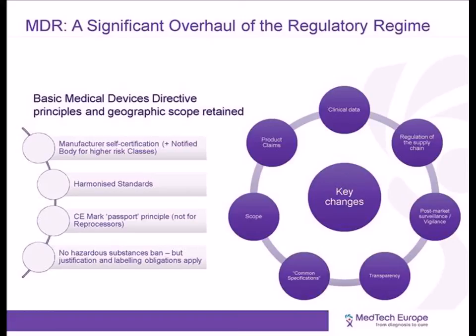Finish up on this slide, two more points. One is common specifications, or CS for short. These specifications are introduced to the medical devices sector for the first time, and they come partially from the in vitro diagnostics sector. These specifications are a little bit similar to harmonized standards, meaning that if you apply them, these specifications give presumption of conformity with aspects of the MDR. However, compliance with these specifications will actually be mandatory, especially for the non-medical or aesthetic devices mentioned earlier. Manufacturers can choose alternative solutions from common specifications, but they must duly justify why they do this whenever a specification exists for the device in question.